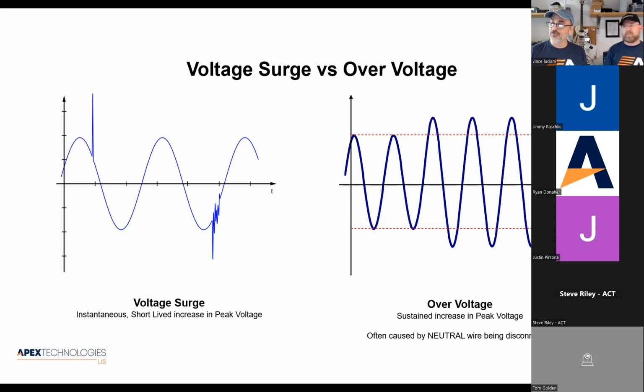The drawing on the right is showing over voltage. A lot of people get confused. A surge is an over voltage. What's the difference? We refer to a surge as those instantaneous spikes. They're also called transient spikes. But Howard, the picture on the right, that kind of over voltage is when the sine wave itself increases in amplitude. Usually when you have a sine wave changing its amplitude, it has to do with the transmission and distribution part of the delivery chain, right?